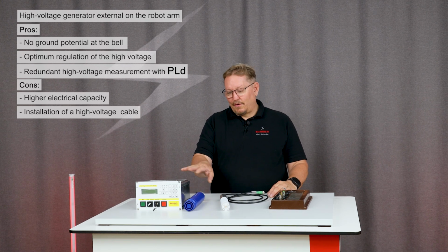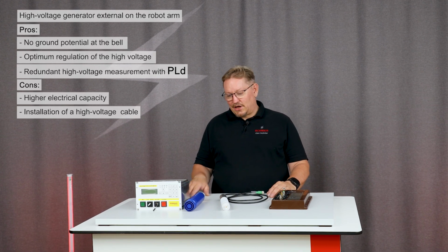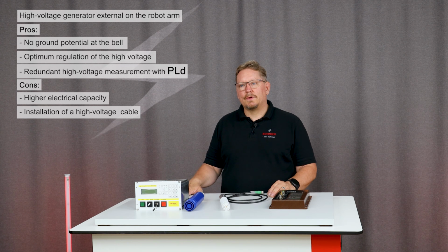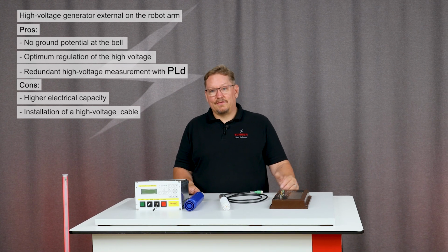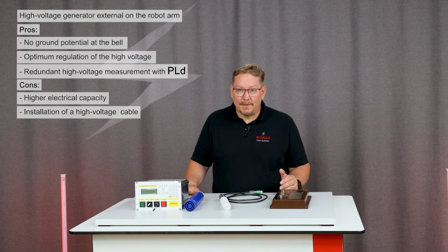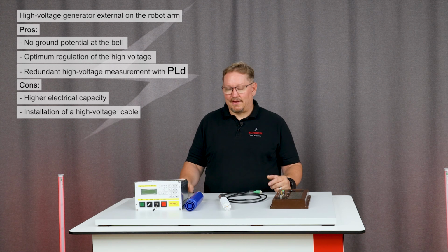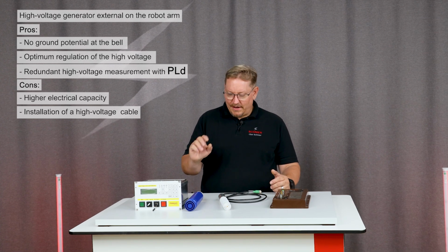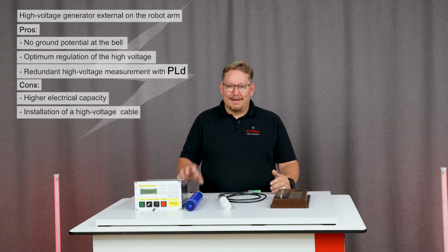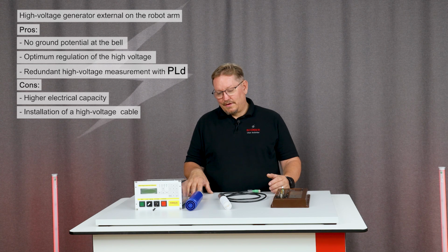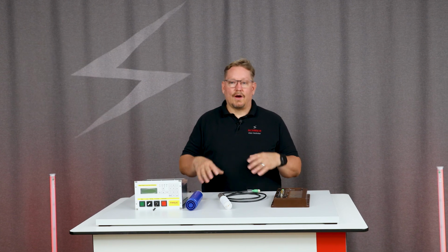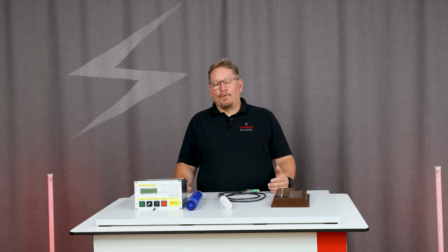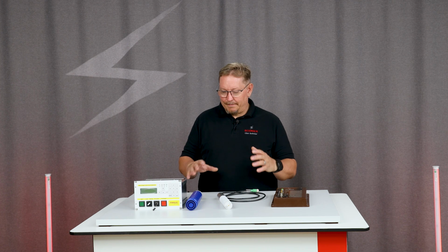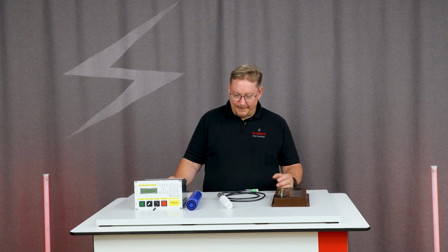We can solve this problem so easily here, because the integrated high-voltage cascades usually don't fit redundant high-voltage measurement in the integrated high-voltage cascades, simply because of the space available, and a safety relay does not fit in twice. This of course means that the user or the system manufacturer has to make a much greater effort to implement the safety concept.